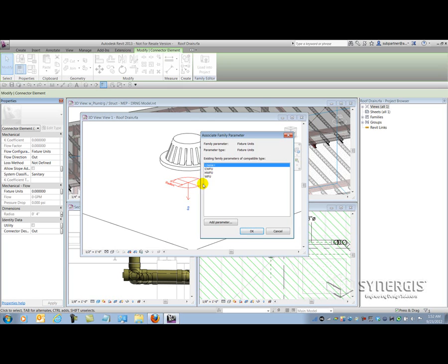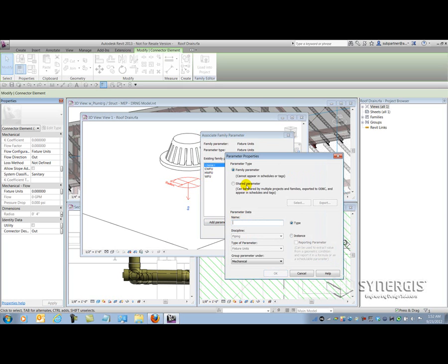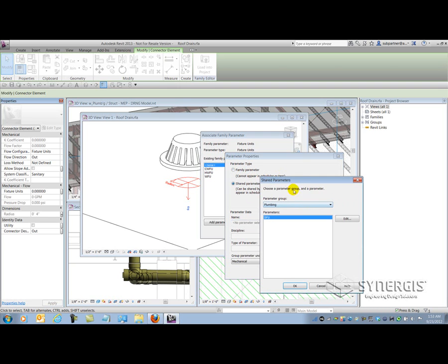The particular parameter I need to create is a shared parameter, because a family parameter cannot appear in schedules or tags. If I want to report on the data about the drains, I need to be able to schedule it or tag it, and the family parameter can't give me that option — but the shared parameter can. So if I select shared parameter and hit the select button, it lets me choose from my shared parameter file. It has a group called Plumbing and a parameter called DFU, which is drain fixture units.